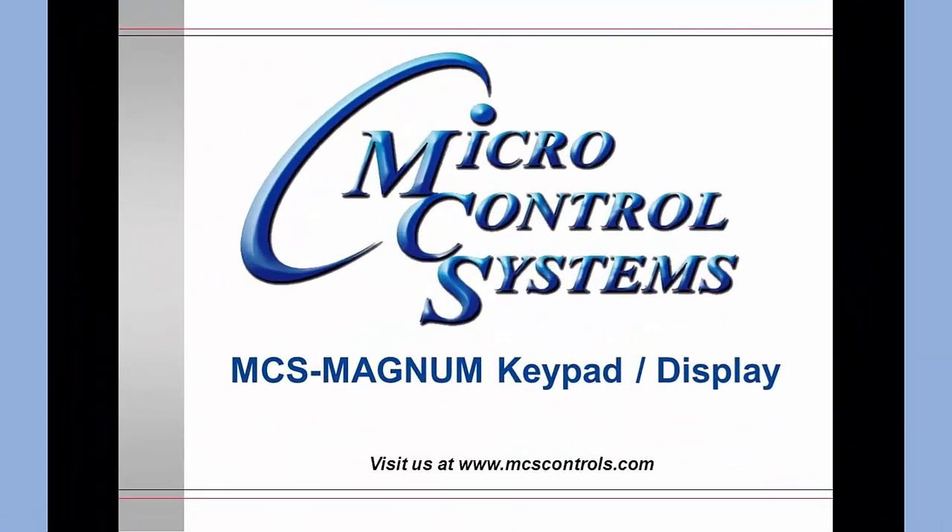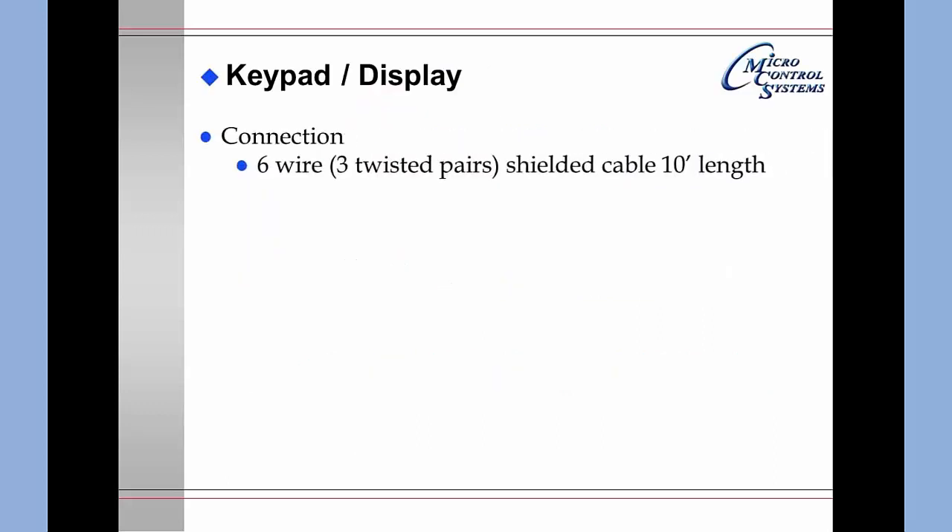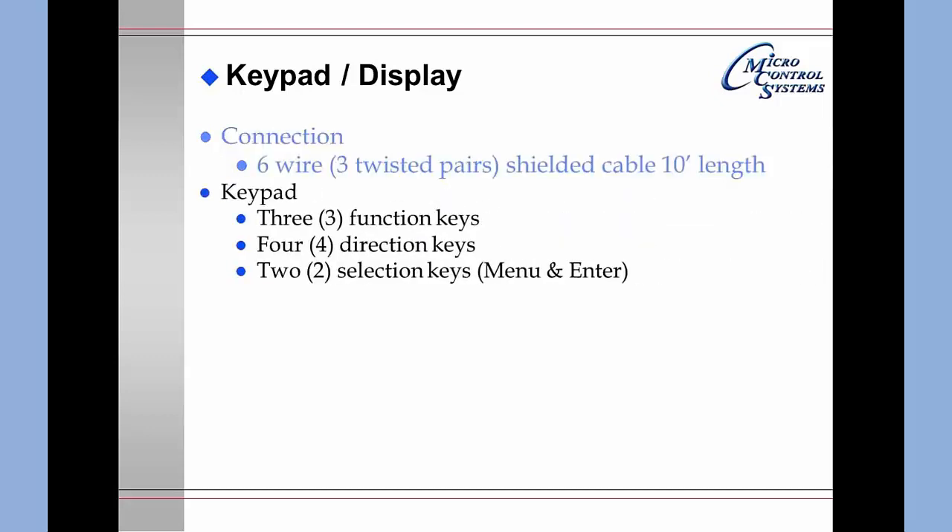Welcome to Micro Control Systems online training video. The current presentation will discuss the MCS Magnum keypad display. The keypad display connection is a six-wire shielded cable approximately 10 feet in length. It consists of three twisted pairs. It is preferable that you do not cut this cable, but leave it in its entire length and coil up any excess cable, tie-wrapping it in an area where it will not be readily accessible to AC noise.